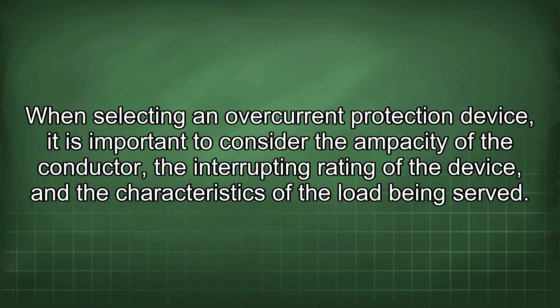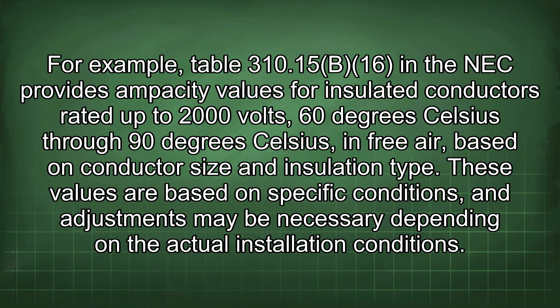For example, Table 310.15(B)(16) in the NEC provides ampacity values for insulated conductors rated up to 2000 volts, 60 degrees Celsius through 90 degrees Celsius, in free air, based on conductor size and insulation type. These values are based on specific conditions, and adjustments may be necessary depending on the actual installation conditions. Article 310.15(C) of the NEC provides adjustment factors for ambient temperature. If the ambient temperature exceeds 30 degrees Celsius, 86 degrees Fahrenheit, the ampacity of the conductor must be derated.